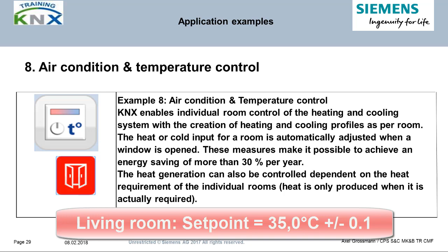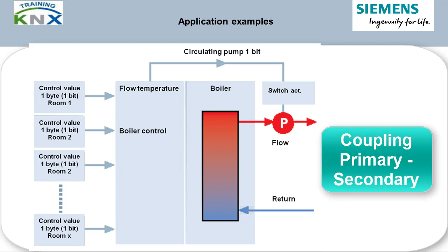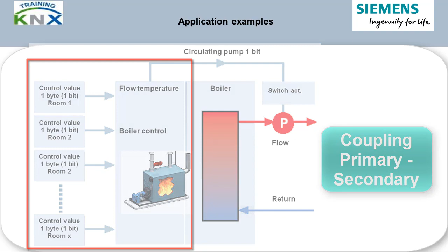In addition, by monitoring of windows, it is avoided to continue with the normal setpoint when the windows are open. It is instead turned to building protection mode. This is either 7 or 35 degrees Celsius, so that you both save energy and avoid building damage by frost or overheating. By the use of the so-called primary to secondary circuit coupling, it is finally achieved that the central energy producers for heating and chilling are controlled by demand. This technique allows the direct management of the flow temperatures in dependence on the requested energy from the individual rooms.